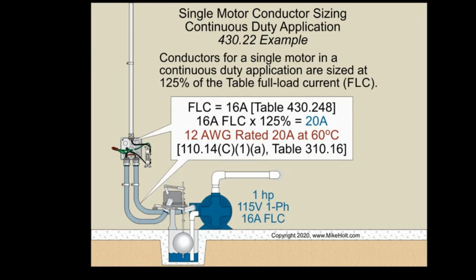20 amps. I'm going to go back to table 310.16. I'm going to look to see what 20 amps is required to be. And it's 12 gauge. And that's how I determine conductor size for a motor. It's literally that simple. I take the FLC, I multiply it by 125%.